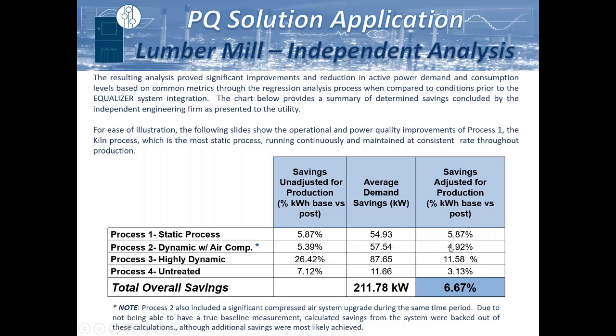There was another area where they did a compressed air system upgrade at the same time, so it was impossible to look at a pre versus post for that condition. We actually think we got a little bit more than that, but it was a lot easier to just take out the compressed air savings. But we also got savings associated with some untreated areas. Prior to the project implementation, when the plant was running, their average voltage was around 470. But when the plant was not in operation, their voltage was about 510, because they had to tap up their voltage to make sure that whenever logs come in and jam up, it doesn't trip a bunch of things out. So this was seen everywhere.